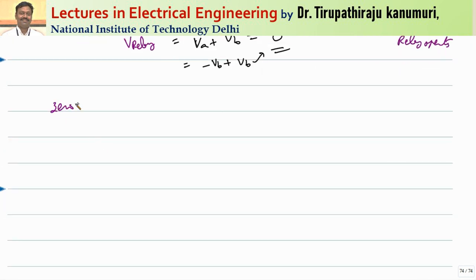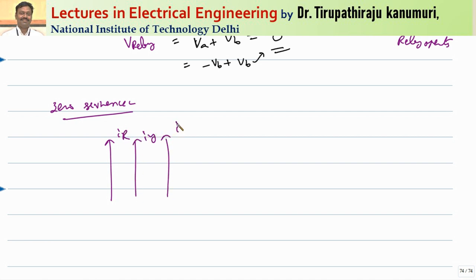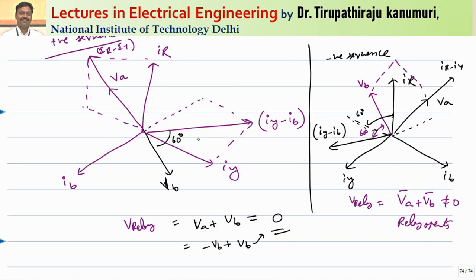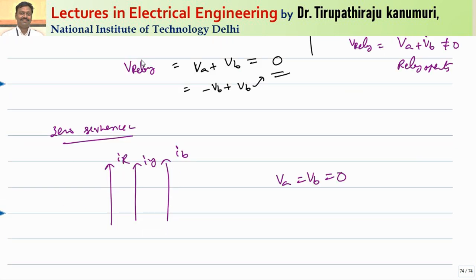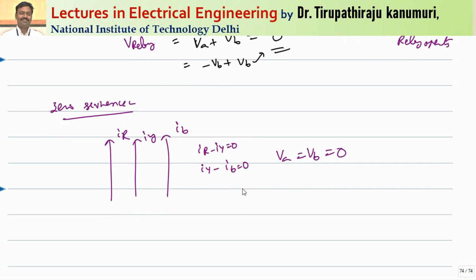For zero sequence components, all currents IR, IY, and IB are in phase. Therefore IR − IY = 0 and IY − IB = 0. This gives VA = VB = 0, so VA + VB = 0 and the relay will not operate for zero sequence components.